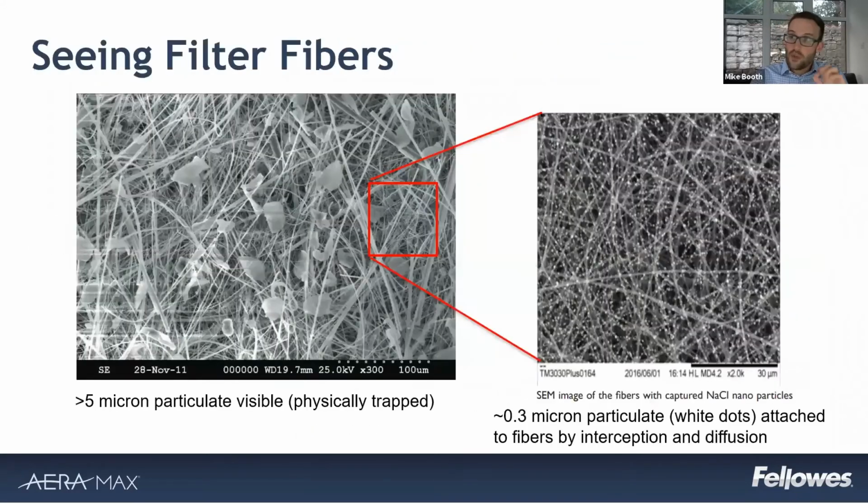If we zoom right in to look at a HEPA filter, what you can see on the left here is the trap method. So things that are larger in size, around 5 microns or above, still not visible to the human eye, are large enough that they're going to be physically trapped by a filter such as a HEPA filter. But if you look on the right hand side, if we zoom in to start to look at the 0.3 micron level, those little white dots all represent particulate matter that's been captured by this filter. Now what you can quite clearly see is that those little white dots could easily fit through the gaps, but they don't, and that's simply because of the way in which a HEPA filter is able to remove those issues from the air. Like I said, because of the different physics methods of how these filters actually work.